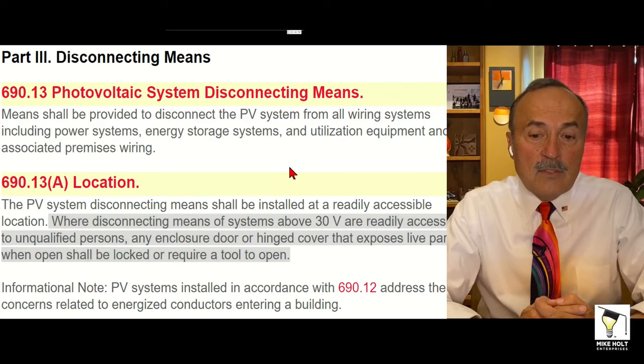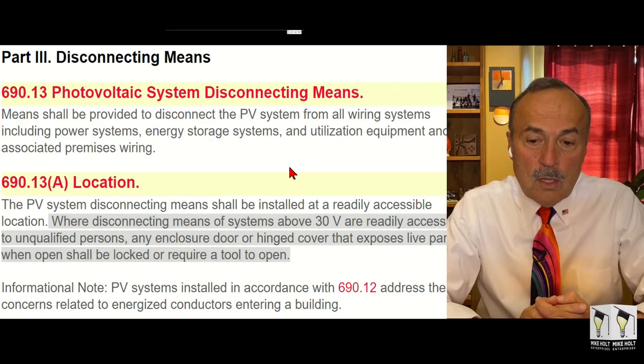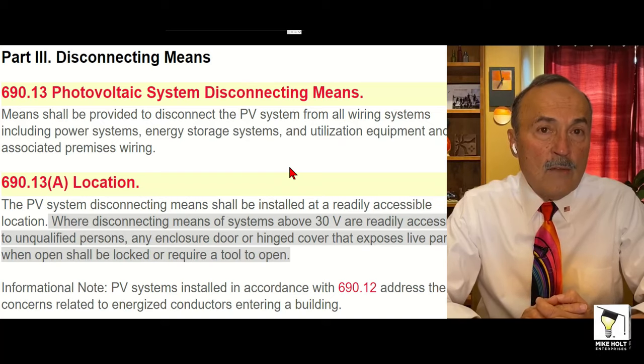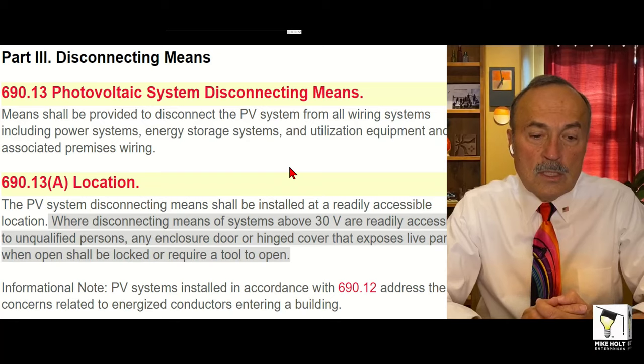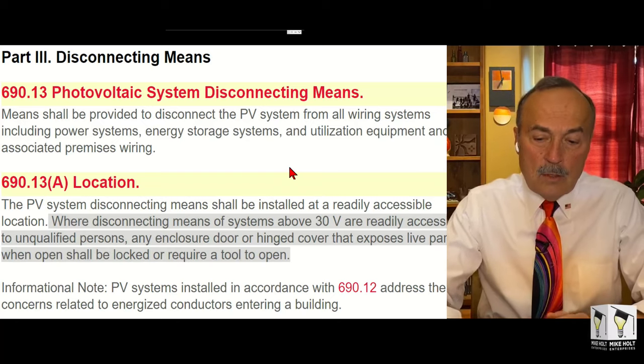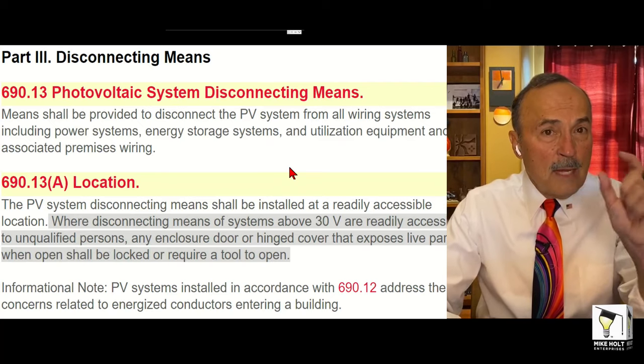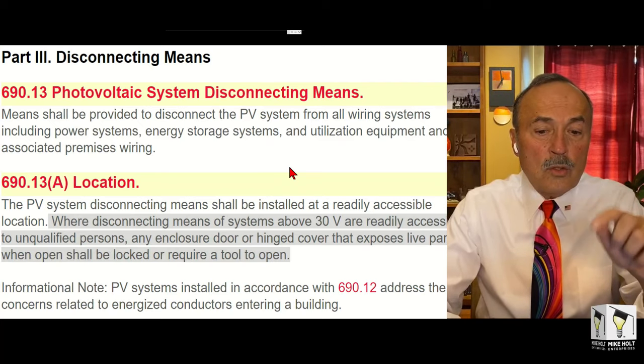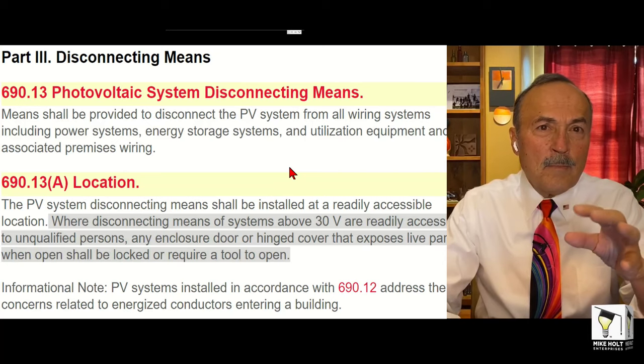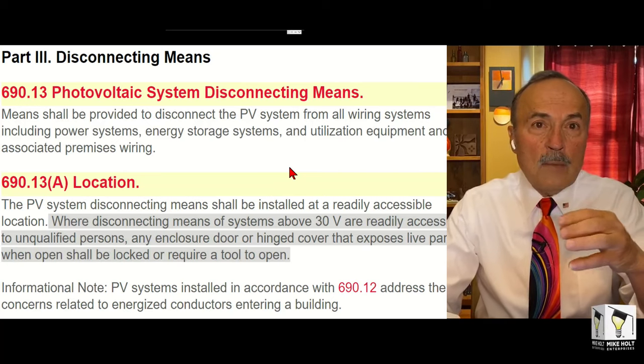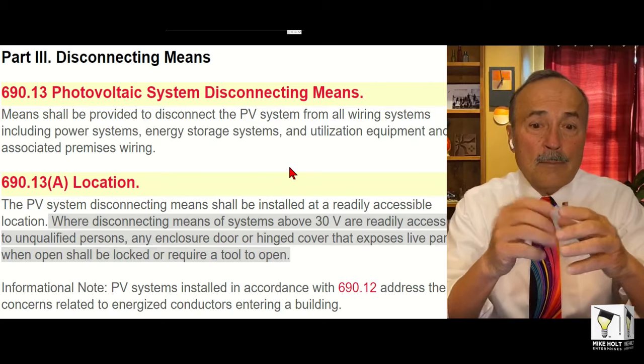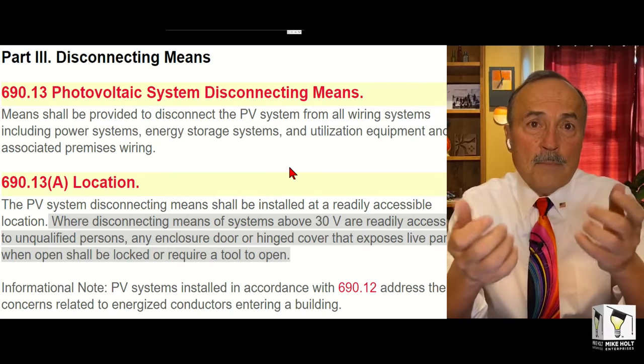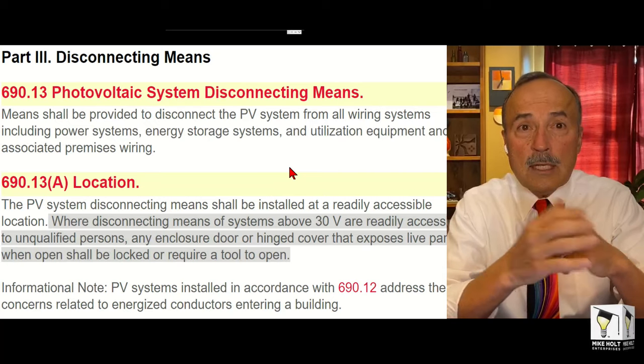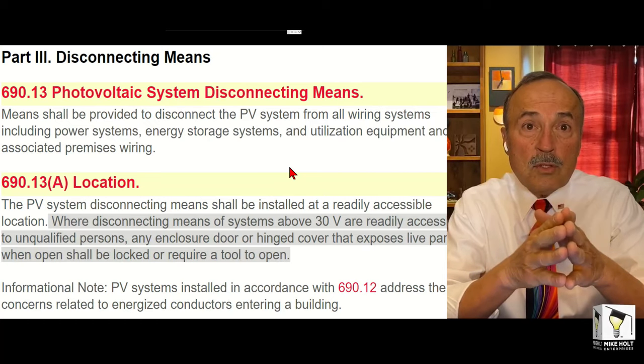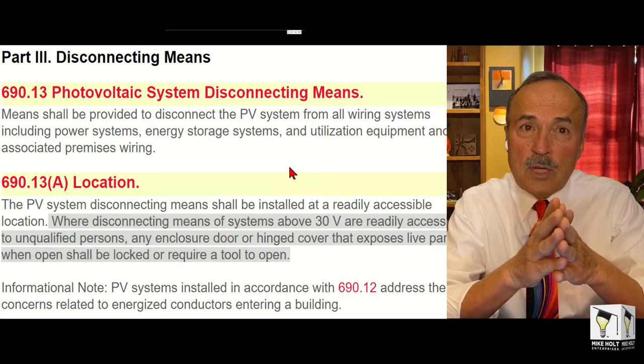Where disconnecting means of systems over 30 volts are readily accessible to unqualified persons, any enclosure door or hinge cover that exposes live parts will be locked or require a tool. So it shall be locked. You put a lock on it or require a tool to open. Now, the code doesn't tell us what kind of tool. I guess you could put a bolt and a nut, and you need a screwdriver and channel locks or some other tool to open it up. So this is a change in the 2020 code.